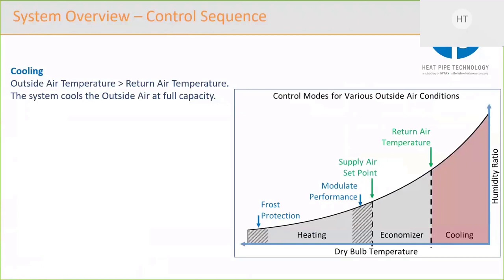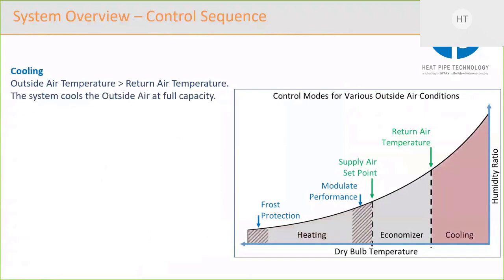So looking at the control sequence, what I've done is I've taken a psychrometric chart and carved it up into different areas. So first of all, we're going to look at the cooling area, the area that's red. And this is when the outside air temperature is higher than the return air temperature. So the return air is being used as a heat sink to cool the outside air. Sorry, just to touch on that. So the system is always at full capacity. Because the outside air can never be cooled below the return air, the pumps will be running full speed to get as much energy recovery as possible.